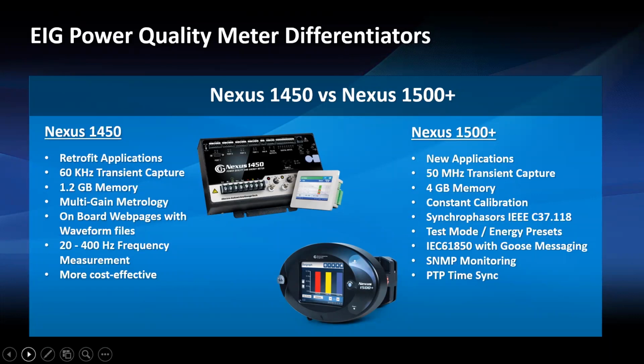So if you want to capture your higher transients, and that's really important to you to be able to measure if there are those high speed transients in your system, the Nexus 1500 Plus might be a good option to go with. The Nexus 1500 Plus also has the IEC 61850 with GOOSE messaging. So if there are any applications for substation automation where they're going down the route of IEC 61850, this is a great meter to use. In addition to that, it also has synchrophasors, which a lot of the utilities and other customers out there are trying to see. Not just in the US, they're just starting to catch up, but in the international market, we see that a lot of research is being done into synchrophasors. So the Nexus 1500 Plus, in addition to being a power quality meter, is actually also a PMU. It is a phasor measurement unit.